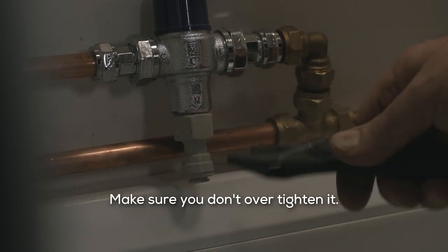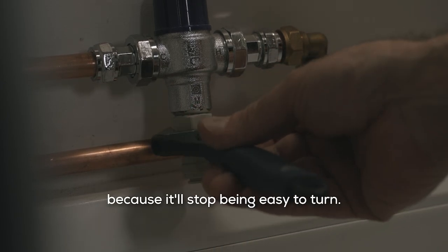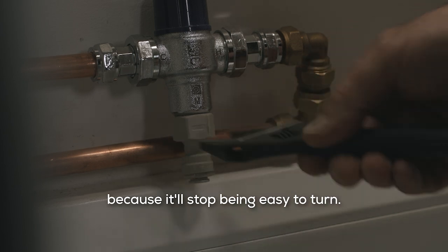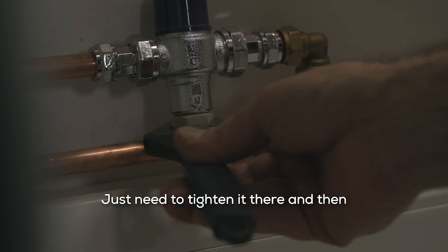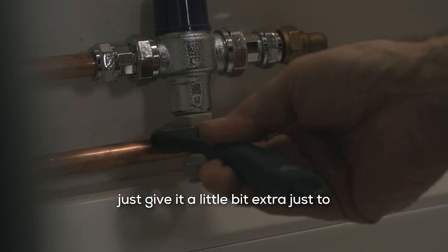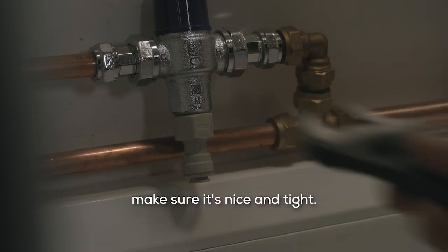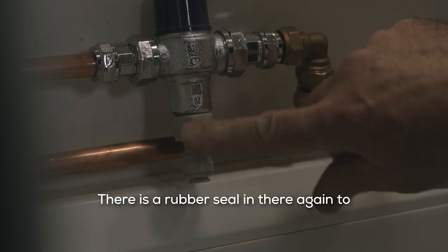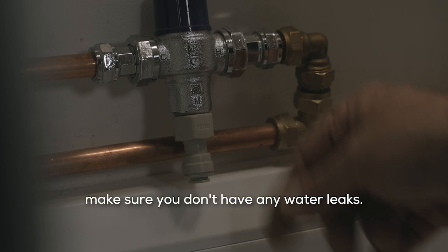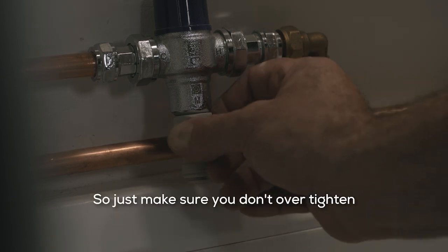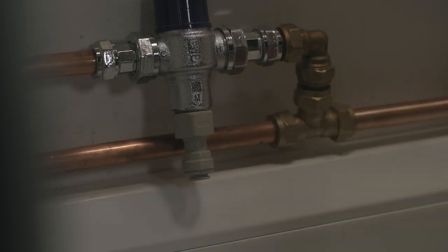Make sure you don't over tighten it. You'll feel if you over tighten it, because it'll stop being easy to turn. Just tighten it there and then give it a little bit extra just to make sure it's nice and tight. There is a rubber seal in there again to make sure you don't have any water leaks. So just make sure you don't over tighten it, that's really important.